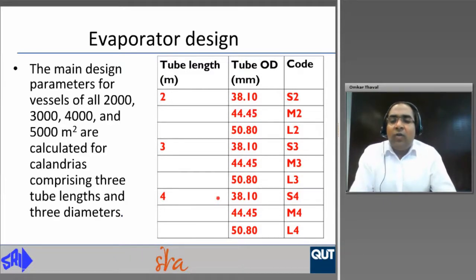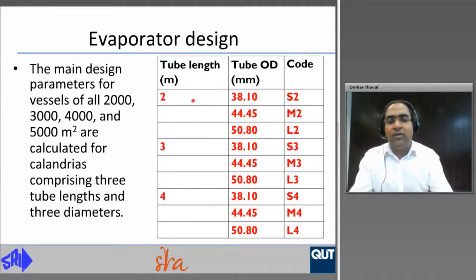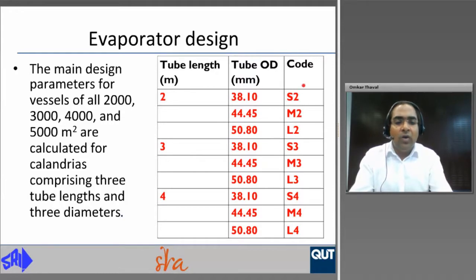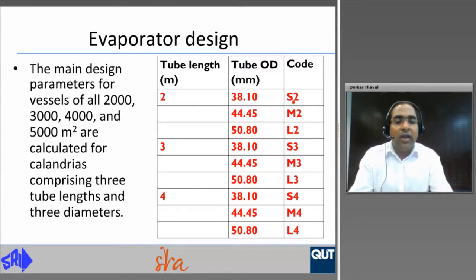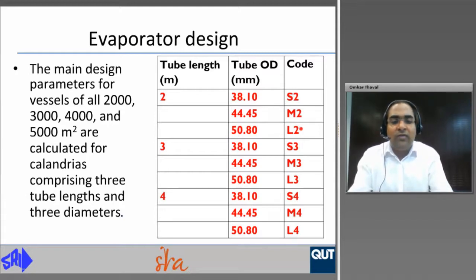The main design parameters for all four heating surface areas are calculated for calandrias comprising 3 tube lengths and 3 tube diameters. Tube lengths of 2, 3, and 4 meters and tube diameters of 38.1, 44.45, and 50.8 millimeters are used. A code is given to each tube dimension: S for small diameter 38.1 mm, M for medium diameter 44.45 mm, and L for large diameter 50.8 mm, with the number representing the tube length. These codes will be referred to throughout the presentation.